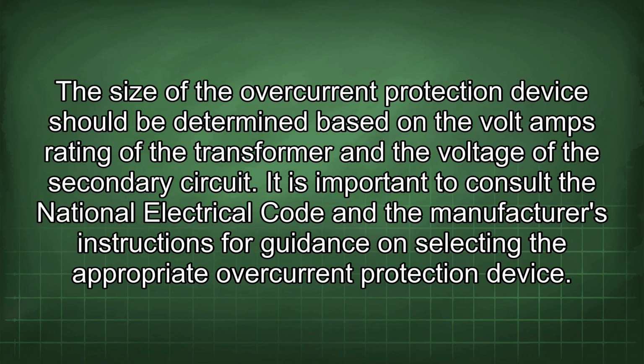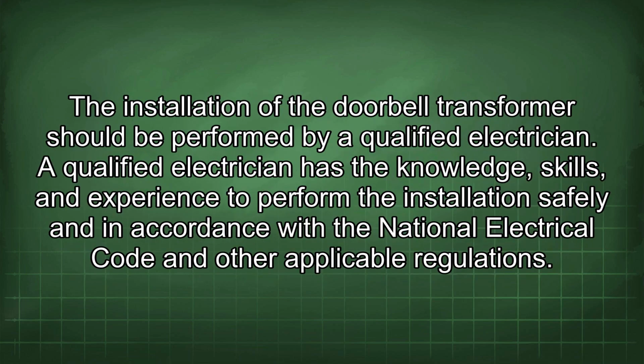The size of the overcurrent protection device should be determined based on the volt-amps rating of the transformer and the voltage of the secondary circuit. It is important to consult the National Electrical Code and the manufacturer's instructions for guidance on selecting the appropriate overcurrent protection device. The installation of the doorbell transformer should be performed by a qualified electrician.